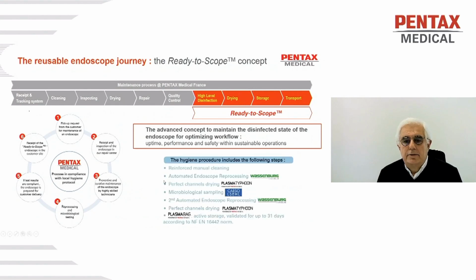If we dig a little deeper into the process: after the repair, we do reinforced manual cleaning, and then automated endoscope reprocessing as usual, with channel drying by plasma typhoon. Then the endoscope waits for 12 hours before our microbiological lab does the sampling, channel by channel. After the samples have been tested by our lab, there is automated reprocessing, drying by plasma typhoon, and storage in the plasma bag, which guarantees that the result of the sampling stays valid for 7 days within the bag, because, as said earlier, thanks to the ozone the bag is a static environment.